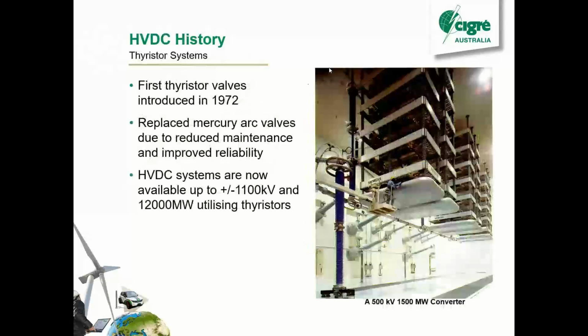So the first Thyristor valves were introduced in 1972, and they've pretty much completely replaced the mercury arc valves due to the reduced maintenance requirements and improved reliability. The mercury arc valves used to require a lot of conditioning. You pretty much always had to have one of the valves out being conditioned to make sure they continued to run correctly. And they did suffer from things called arcbacks. I remember when I first started, we still had the mercury arc valves and we used to have issues with those. But going to the Thyristors pretty much eliminates those problems.